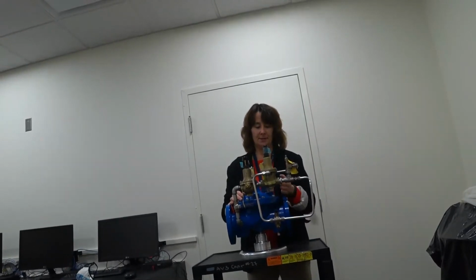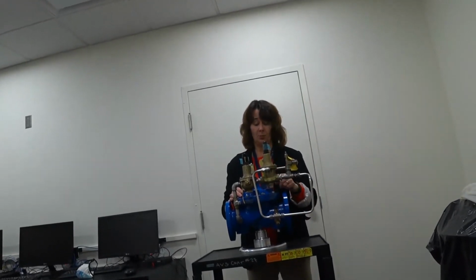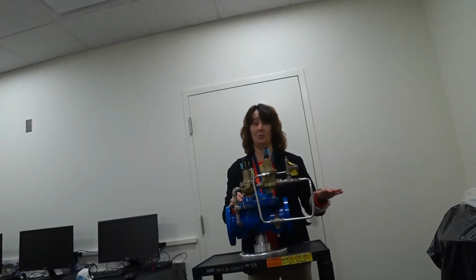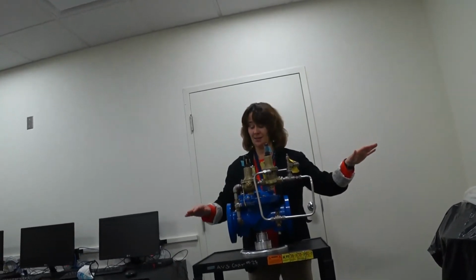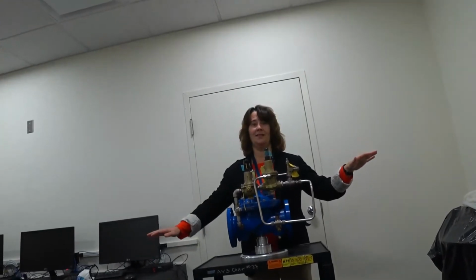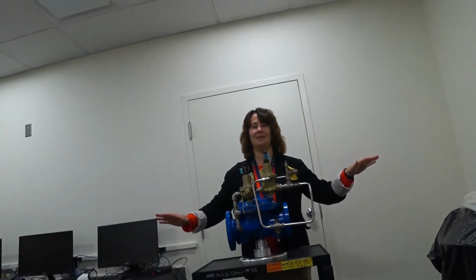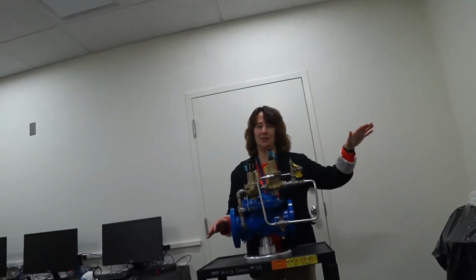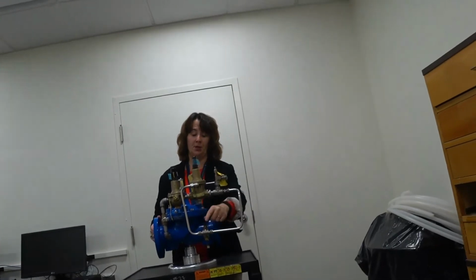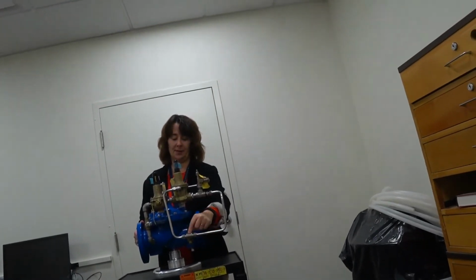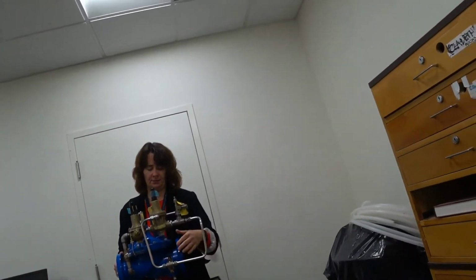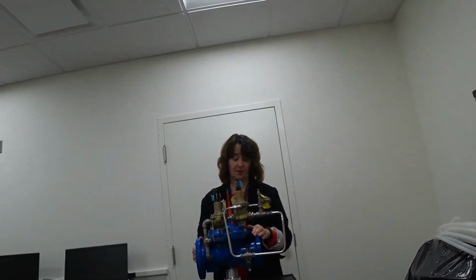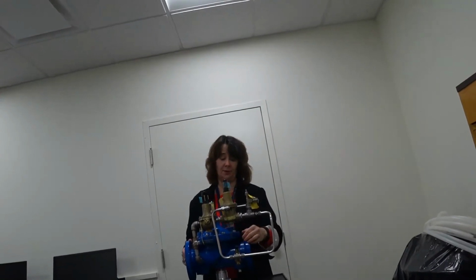So this valve here, the CRL, will close this valve if you drop below the minimum pressure that it wants to maintain in this neighborhood. And it says, regardless of what the downstream people want, I don't care. You don't get it. I'm going to make sure that the upstream people keep their pressure that they want. So let's say this valve is set at 100 psi, and your upstream pressure is above 100 psi, let's say it's 120 psi.